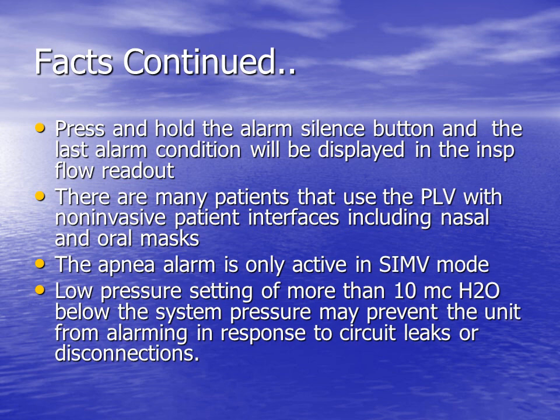Many vents have the ability to display the last alarm condition, and so does the PLV. Press and hold the alarm silence button, and it will display the reason the vent last alarmed in the inspiratory flow window. The PLV may be utilized to deliver non-invasive ventilation via a mask. The apnea alarm will only be functional in SIMV mode, and as with many ventilators, keep in mind that if you set your low pressure alarm at more than 10 below the system pressure, it may not be accurate enough to respond to leaks or disconnections.